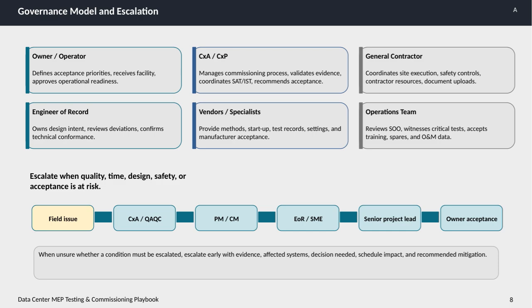Importantly, the model highlights when escalation is needed. Specifically, any issues related to quality, schedule, design, safety, or acceptance risks must be escalated promptly. When a field issue arises, the escalation path can involve the CxA or QA/QC team, the project manager or construction manager, the engineer of record or subject matter experts, the senior project lead, and finally, owner acceptance. If there is any uncertainty about whether a condition requires escalation, the best practice is to escalate early. Include all relevant evidence, identify affected systems, specify the decision required, note any schedule impact, and recommend mitigation steps.